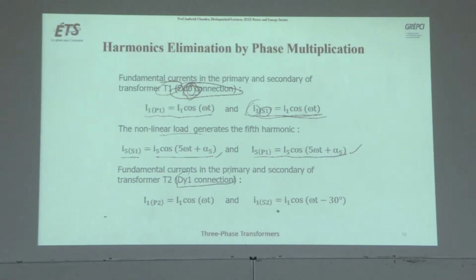Now see the second transformer, DY1. This is the primary side current of the second transformer, and on the secondary side, this is one connection. The secondary side voltage is lagging behind by 30 degrees, so the current is lagging behind by 30 degrees.